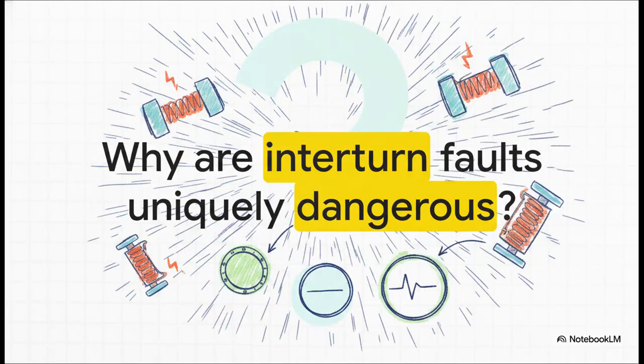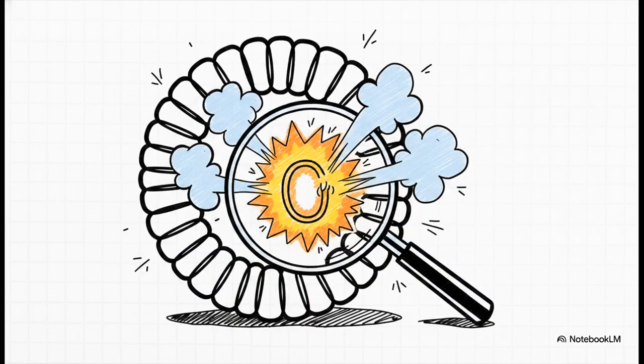But here is a really critical question, and honestly, it's a trap a lot of newcomers fall into. Why is an interturn fault uniquely dangerous, especially considering that to an operator looking at a screen, the total load current being drawn by the transformer might look completely and totally normal? The crucial point here is understanding the physics of a shorted turn. It acts exactly like a pressure cooker.